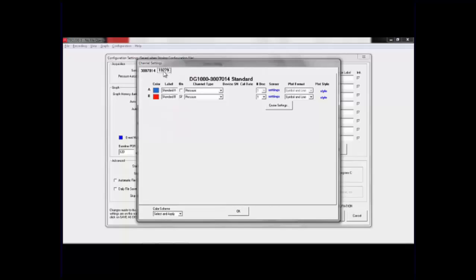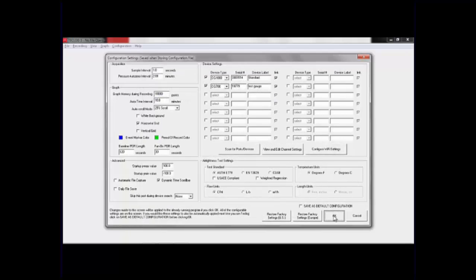And then I'm going to click on the DG700 tab on that serial number, so it says across the top DG700 along with its serial number and its name. And we left that in pressure. We could choose between interior pressure, envelope pressure, Model 3 fan flow, duct blaster flow. We left it at the default pressure, changed the colors, and gave them labels. So click OK there. I'm going to click OK here and go to recording, start recording. Now it's going to scan for the devices, and now it's going to do the handshake with the devices it's finding, and it'll start sending data.